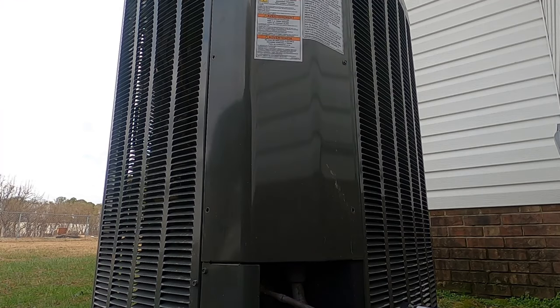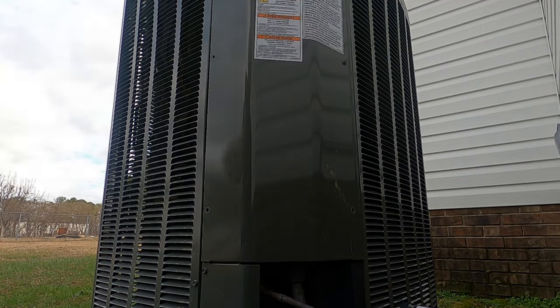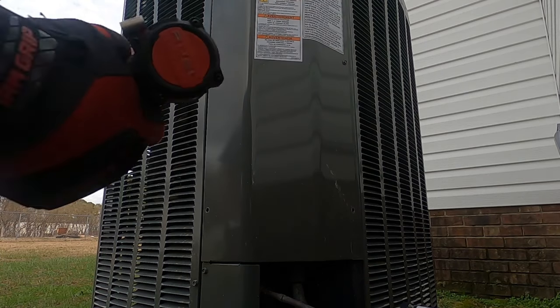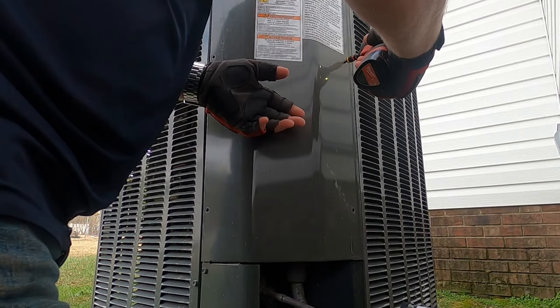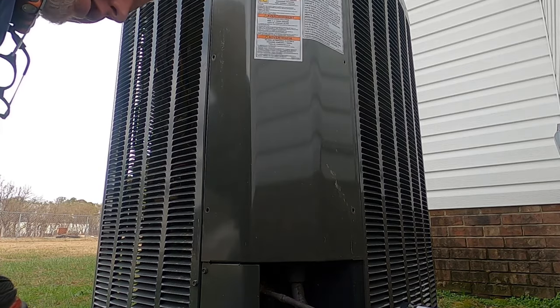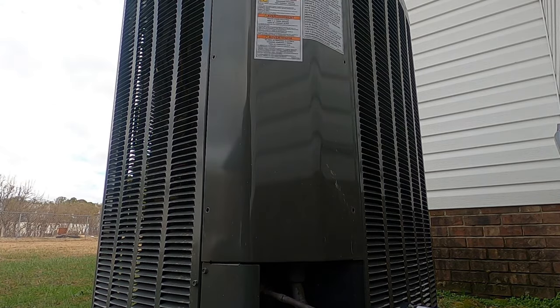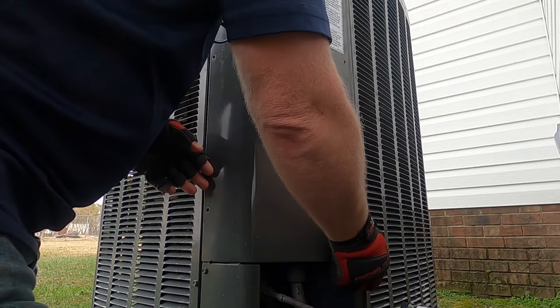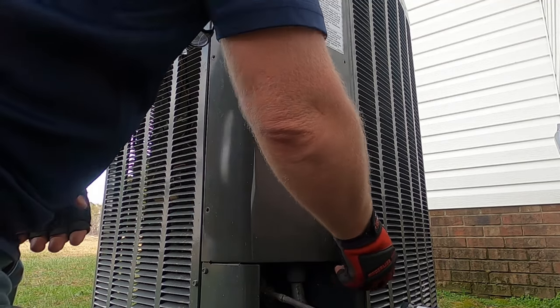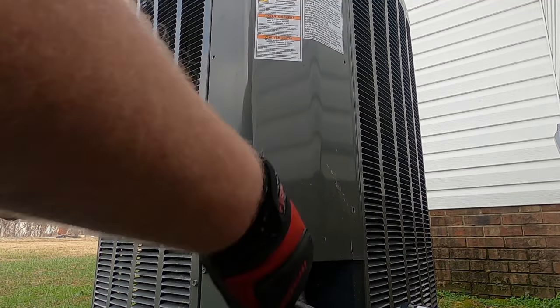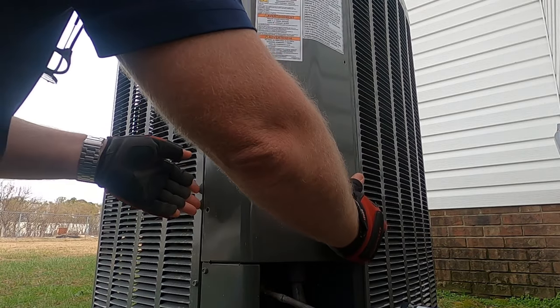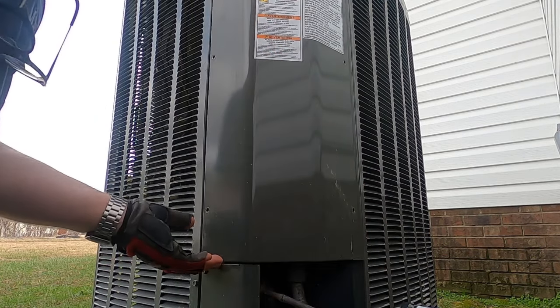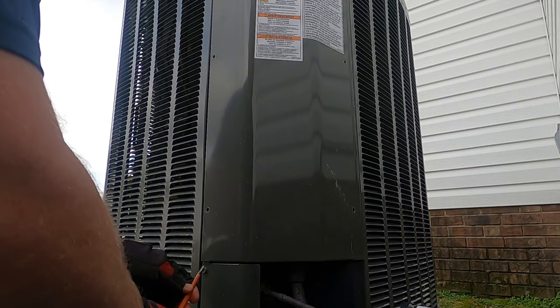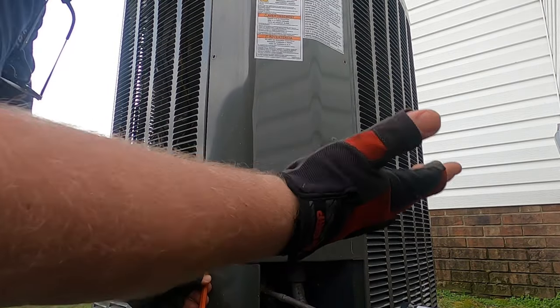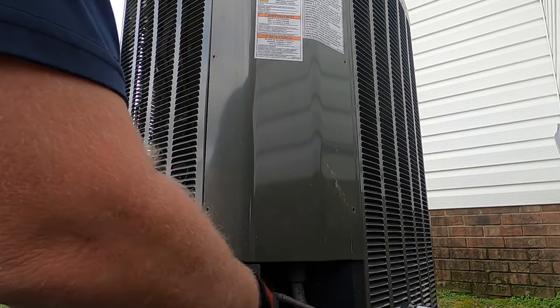But the last alert code on the thermostat was on the 13th of this month, and it wasn't a major alert. The red alert at the bottom was it lost its time clock or something. Not too uncommon with these. Most common problem with these XV units is when you get a quick power surge or a power flicker, you get the faults for loss of 230 volts AC voltage. Then you get another alert for below 180 something DC voltage. That just means the drive discharged because it lost power coming to it from the house.